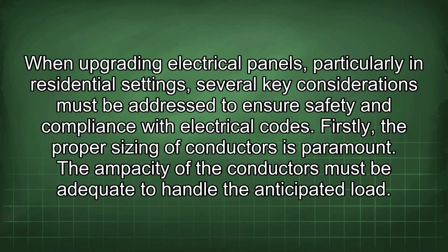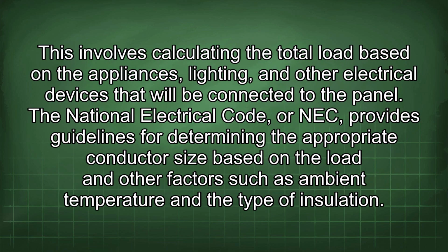When upgrading electrical panels, particularly in residential settings, several key considerations must be addressed to ensure safety and compliance with electrical codes. Firstly, the proper sizing of conductors is paramount. The ampacity of the conductors must be adequate to handle the anticipated load. This involves calculating the total load based on the appliances, lighting, and other electrical devices that will be connected to the panel. The National Electrical Code, or NEC, provides guidelines for determining the appropriate conductor size based on the load and other factors such as ambient temperature and the type of insulation.